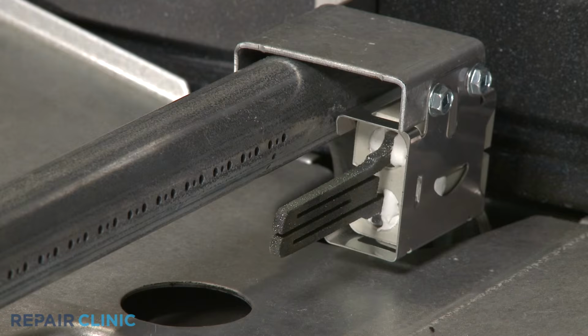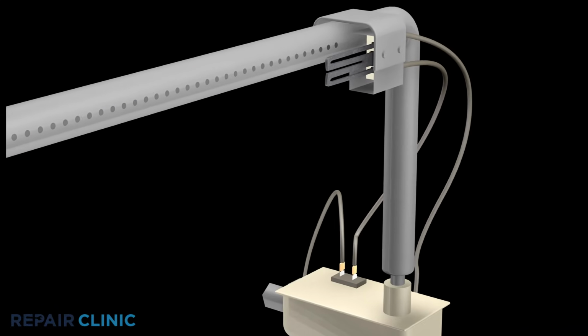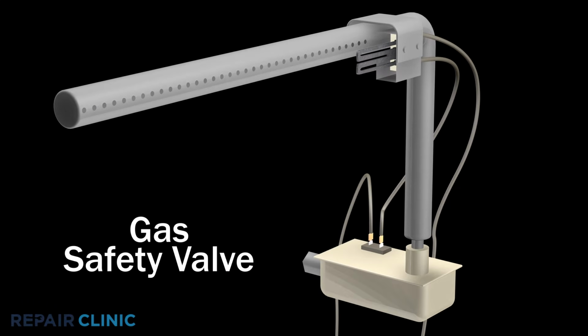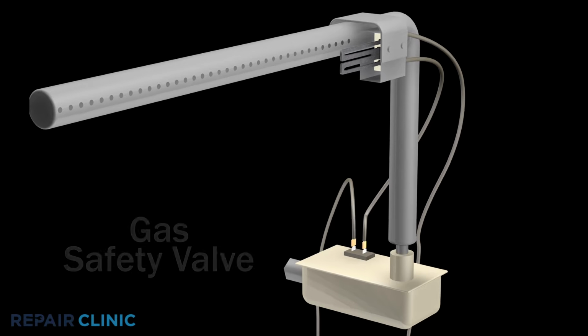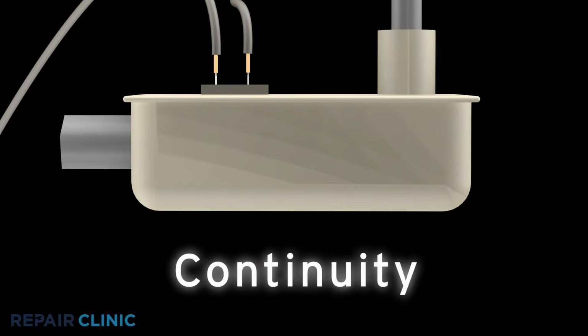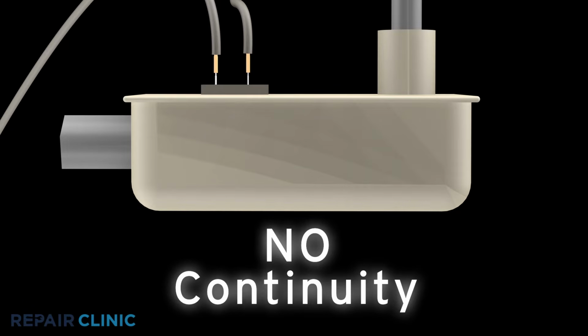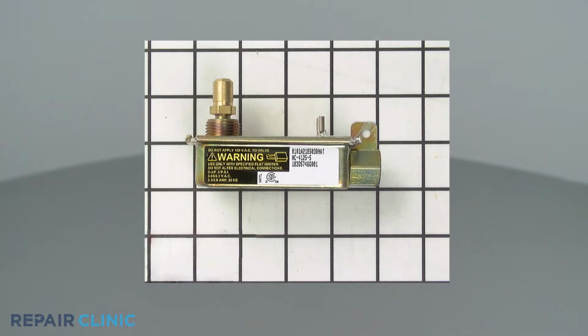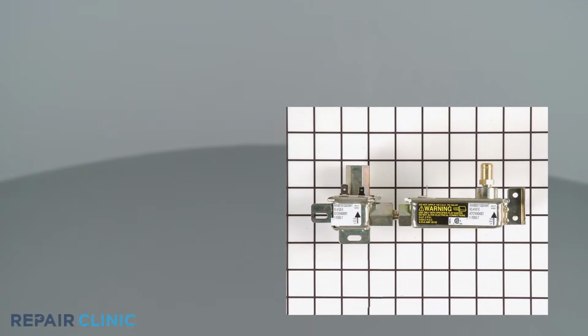If the igniter is not glowing, the cause could be a defective safety valve, and you should test the valve for continuity. A continuity test will determine if a continuous electrical path is present in the valve. If there is no continuity, the electrical path is broken and the safety valve is defective. Valves come in many shapes and sizes, but all of them can be tested for continuity.